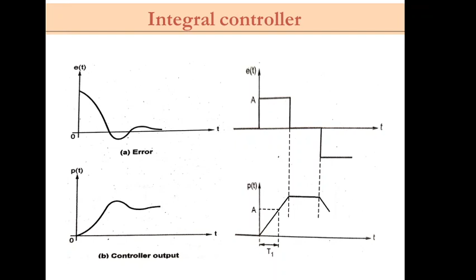Now, in comparison of the proportional and integral modes: in the initial behavior, the P-type controller, that is the proportional controller, acts immediately according to the proportional gain. In the case of integral, it acts slowly and it is the time integral of the error signal. If you check the steady state behavior, in the case of proportional gain, offset error is always present, as we have seen while discussing the proportional controllers, and the larger the gain value, the smaller the error. But in the case of the integral controller, the error signal always becomes 0. There is no offset present in the case of the integral controller.